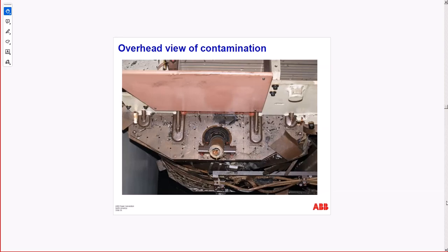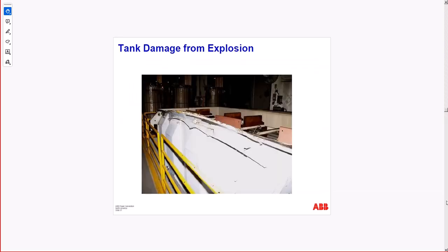It happened not on a transformer but on the UPS class 2. We had this event, and since then we have the FME procedure, foreign material exclusion. So you need to cover with blankets when you drill and use magnets to clean up anything that is around, and use the vacuum cleaner. And there is a full procedure to avoid this kind of thing. Take it very seriously. Any filings like this inside the electric system are a big danger, a huge danger.